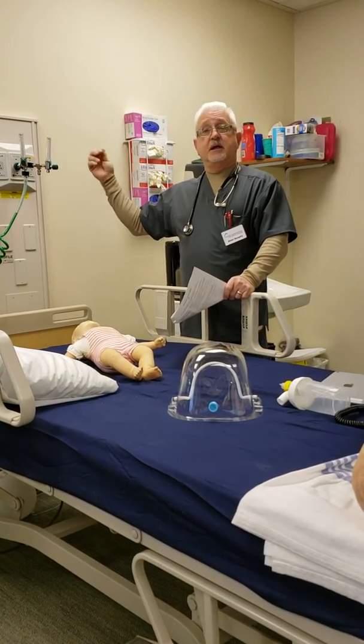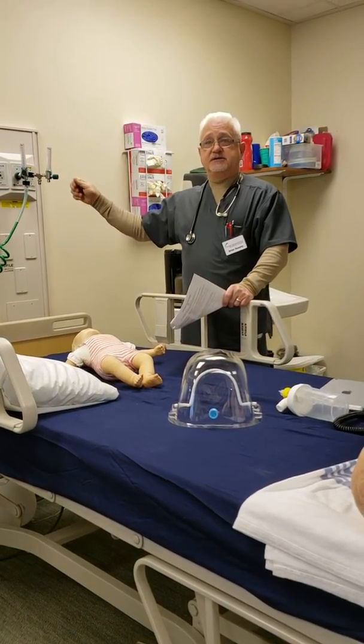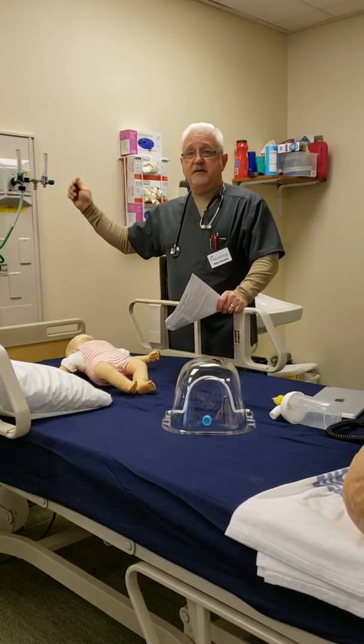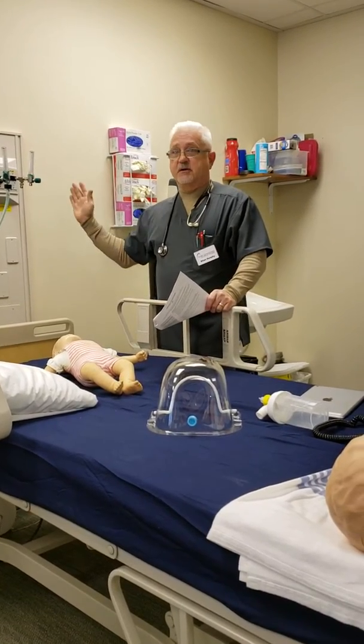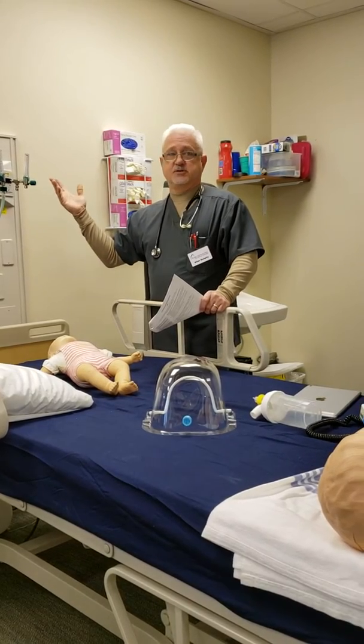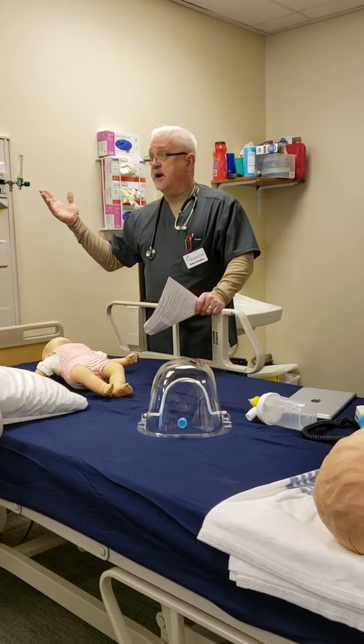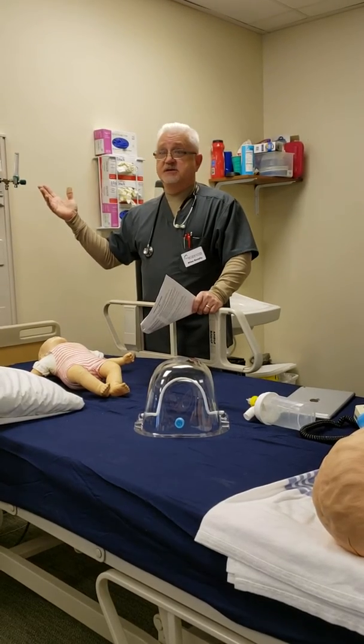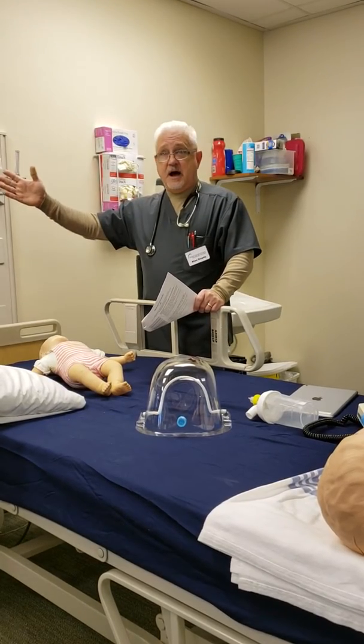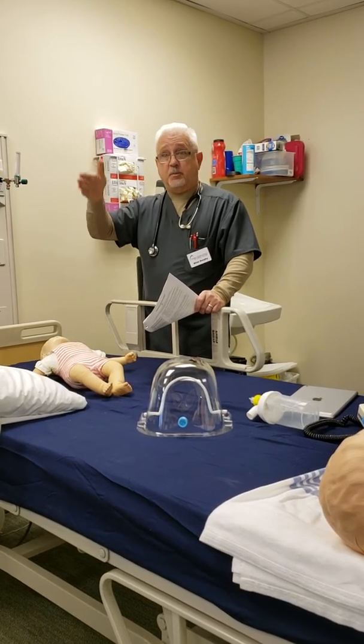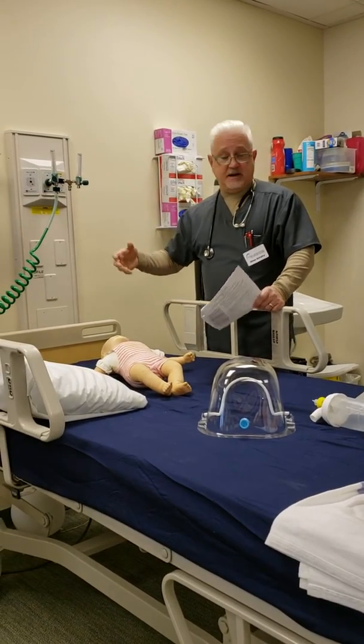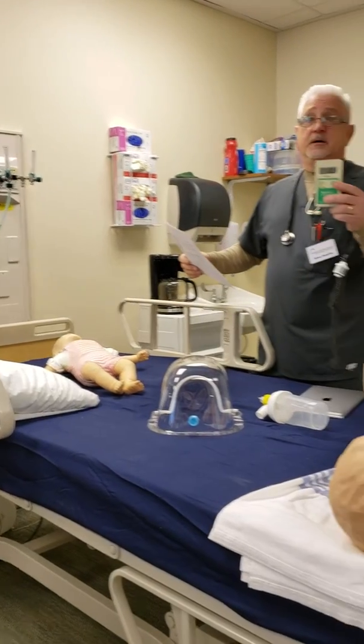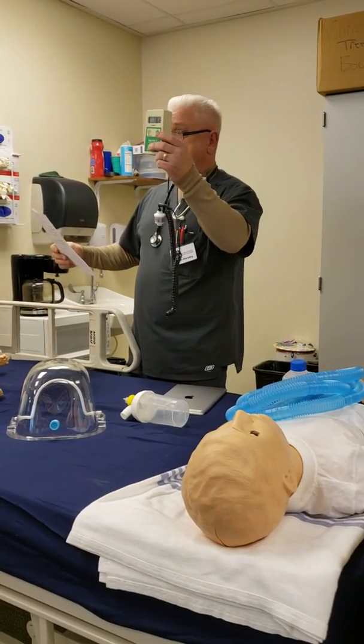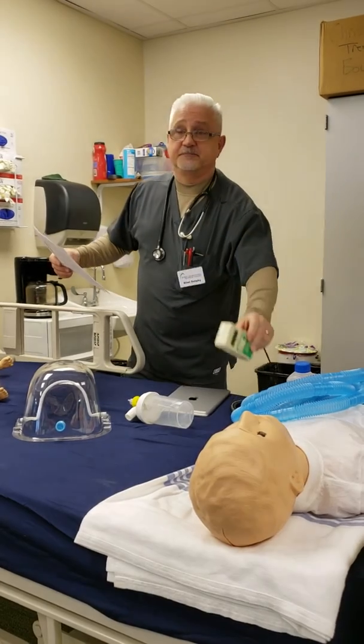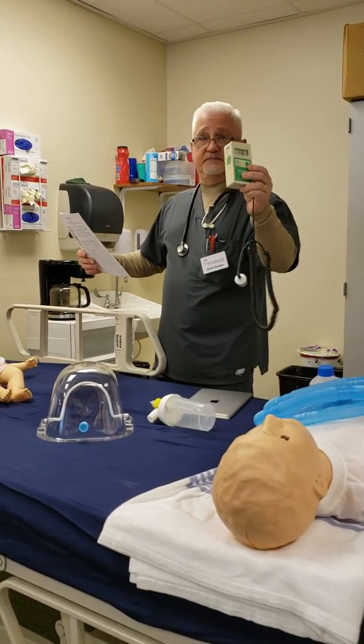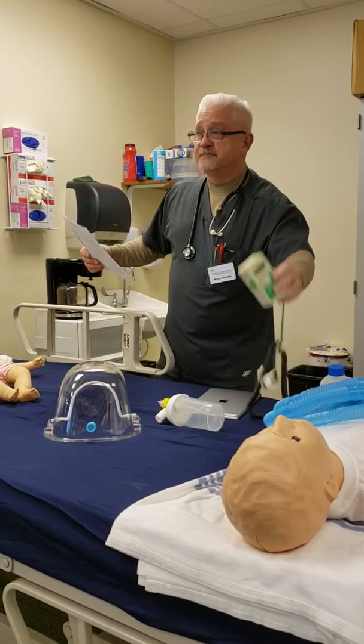Remember that the oxygen blender utilizes a proportional valve to set the air to oxygen ratio that we've talked about before. So if the baby was on 28% oxygen, that's a 10-to-1 air to oxygen ratio. For every 1 part oxygen, I'm going to mix 10 equal parts of air to get the 28%. Then I'm going to confirm that the FiO2 is actually there by using the O2 analyzer, and with your O2 analyzer, you would have done your 2-point calibration.